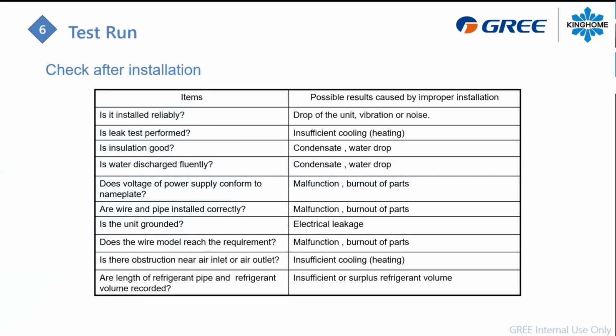When you have done all your installation, so wiring is good, piping is good, the clearance is good, everything is awesome, make a quick check over the unit to see that it's properly installed. Confirm your voltage. Make sure you have good voltage from the panel before turning on the unit, to not damage the board in any way. Make sure you don't have water or anything around the unit. Make sure everything is clean, the clearances are respected, and you have your proper ground. This is really important.